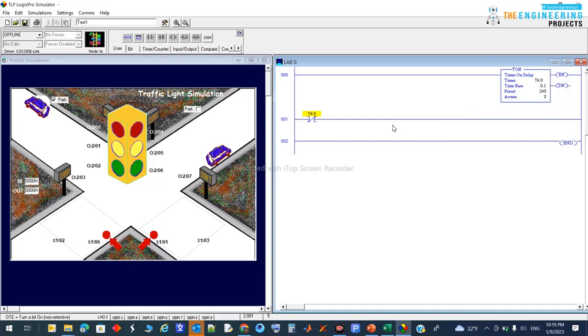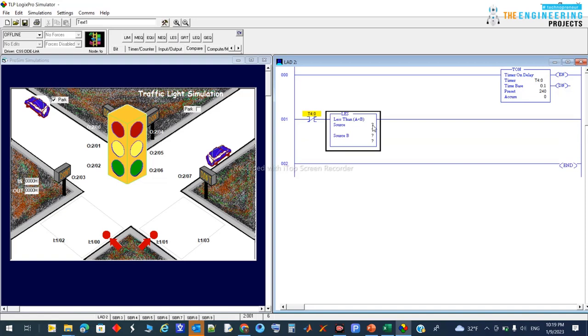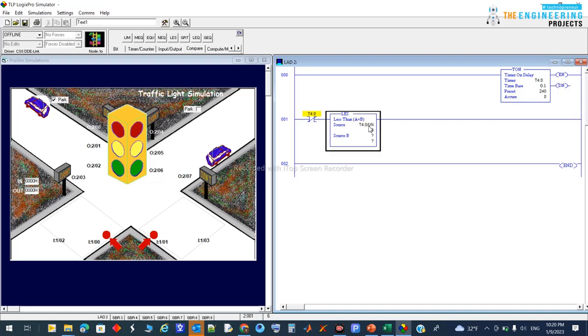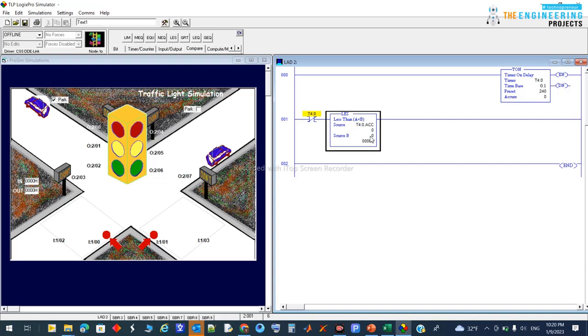I'll use a comparison instruction. I will add a compare: if T40's accumulator is less than 120 — meaning 12 seconds — then I will run the red color output. So if the accumulation is less than 120, the red light will be on.